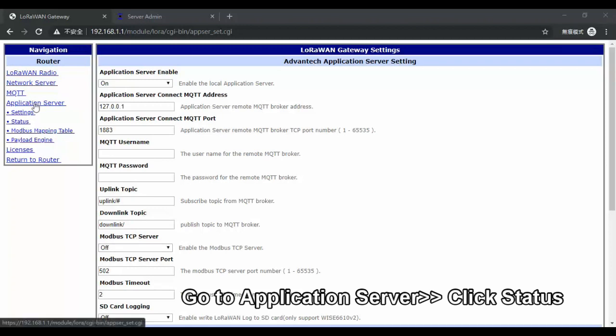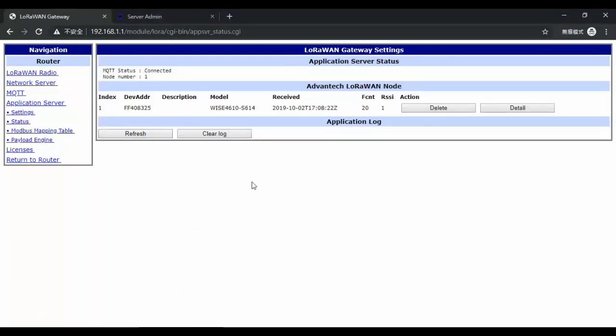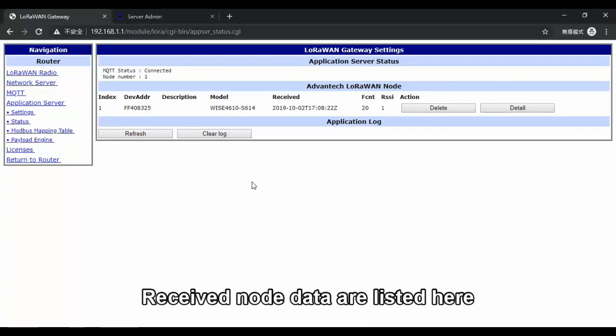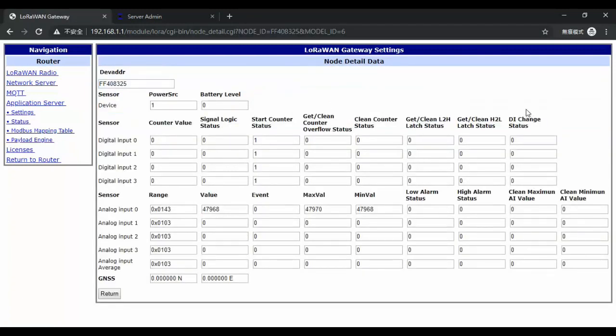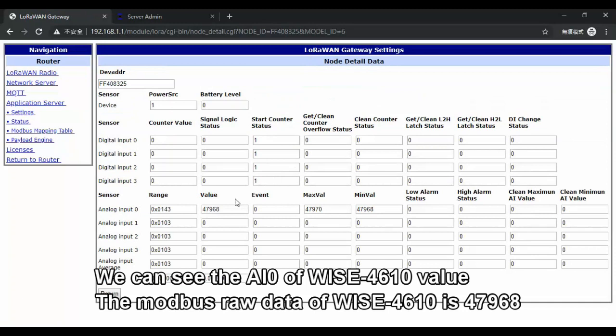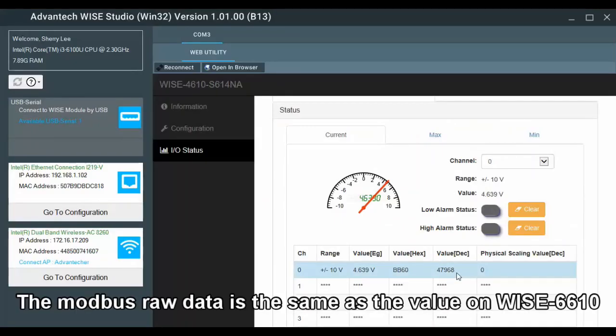Go to Application Server and click Status. Under the Application Server status, you can see the received node data here. As you can see, the device address shown is the WISE-4610 we are using right now. Click Detail for the IO data. Here we can see that AI channel 0 for the WISE-4610 shows this value. The analog raw data shown on AI channel 0 is exactly the same as on the WISE-4610.